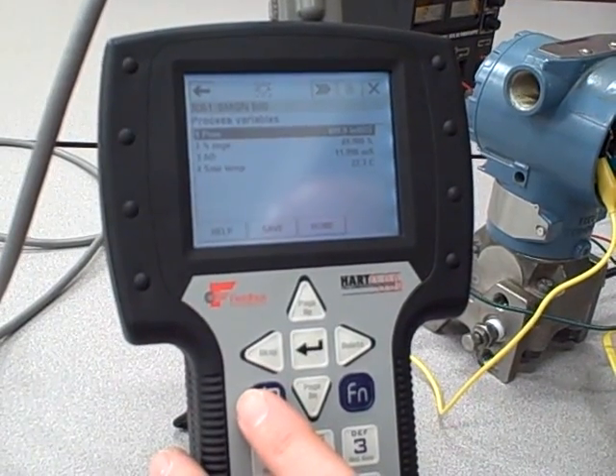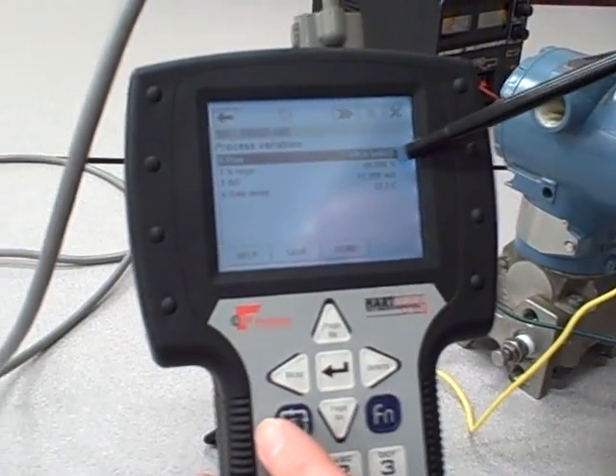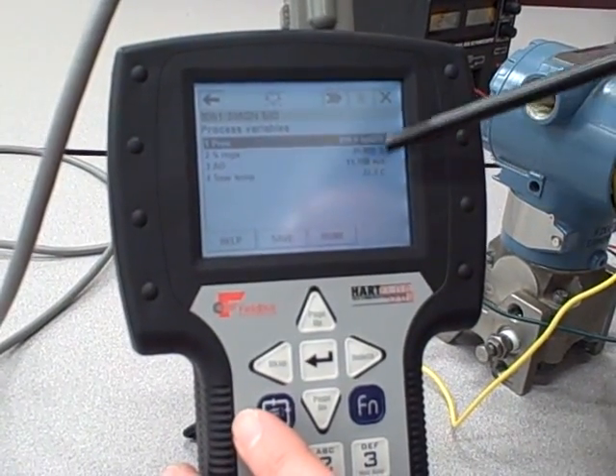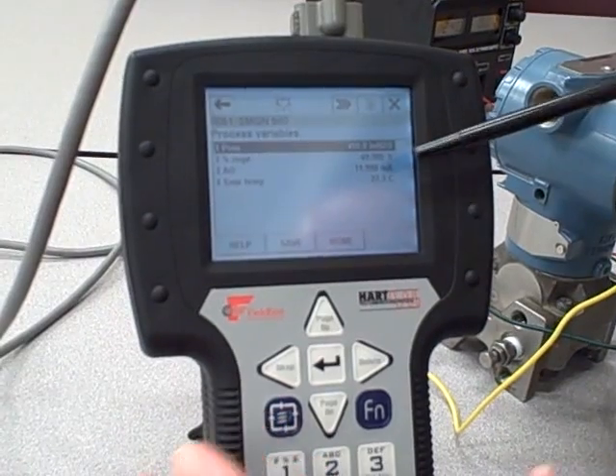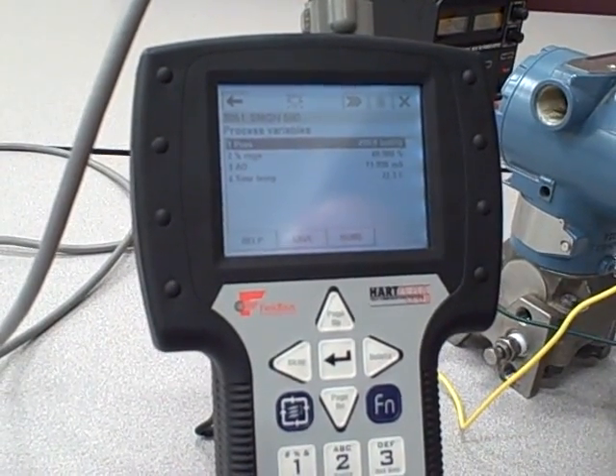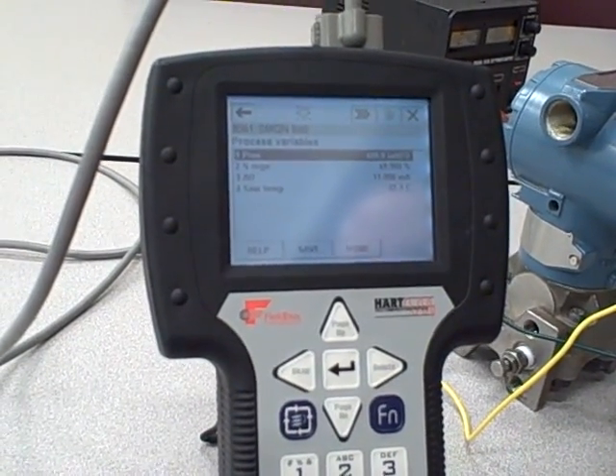As I said before, it was about 500 inches of water column. That is approximately 50% range on the transmitter for a 0 to 1,000 inch range. Analog output about 11.998 or 12 milliamps, and sensor temperature. This is the ambient temperature of the differential pressure sensor at room temperature, about 22 degrees Celsius.